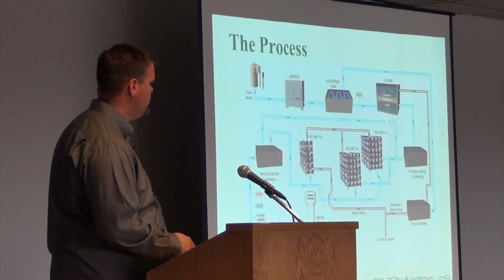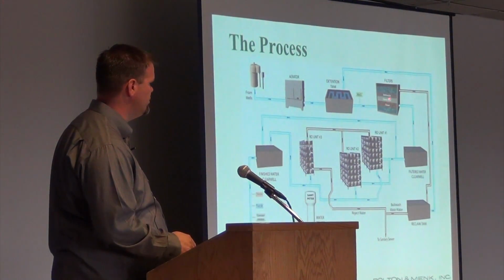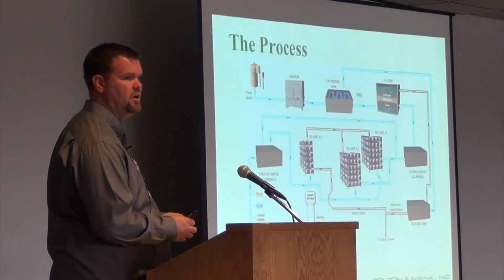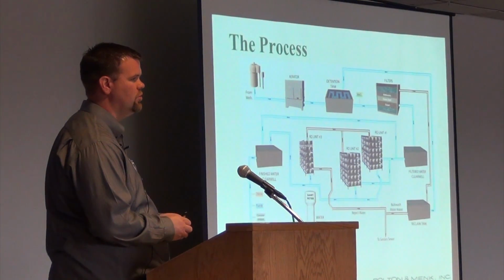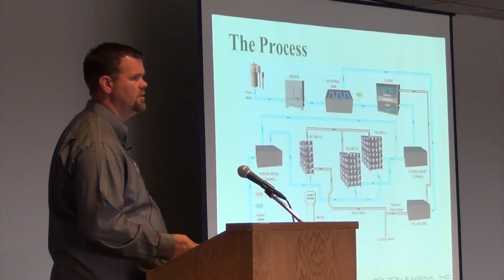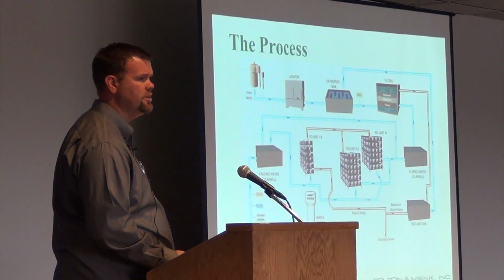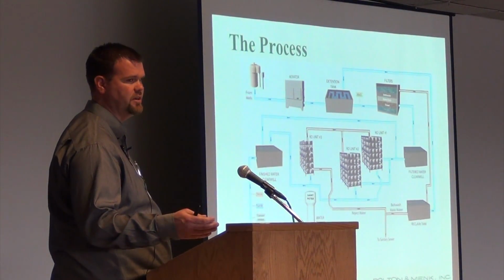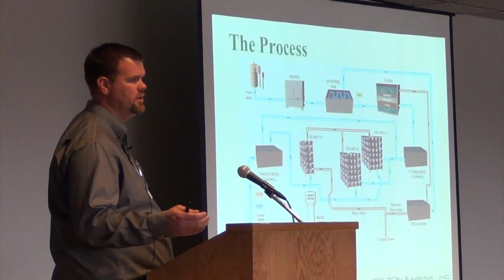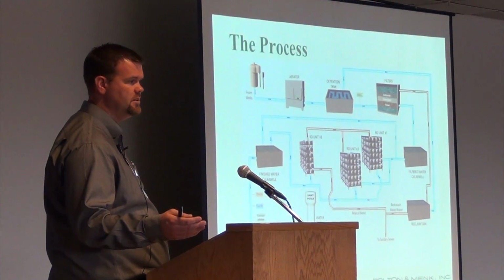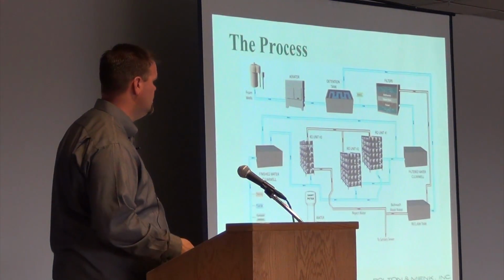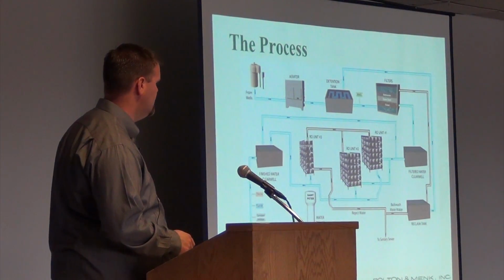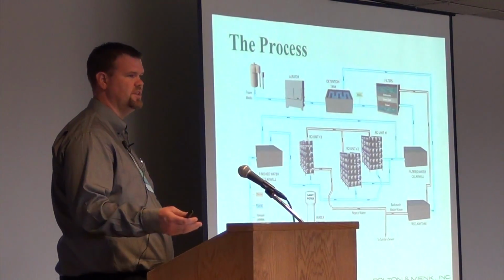For that, what we do is we blend in part of the water from the gravity filter. So we're only using a portion of the RO water, and that way we control that blend and decide what kind of hardness, how much sulfates, the different things in the drinking water we want to send out that will be acceptable to the residents and what they want to use. And so we blend RO water with filtered water to come up with the water that we're sending out.